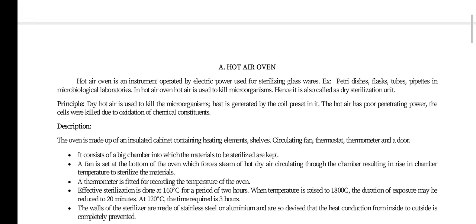Hence, it is also called a dry sterilization unit. Dry hot air is used to kill the microorganisms. Heat is generated by the coil present in it. The hot air has poor penetrating power. The cells are killed due to oxidation of chemical constituents.